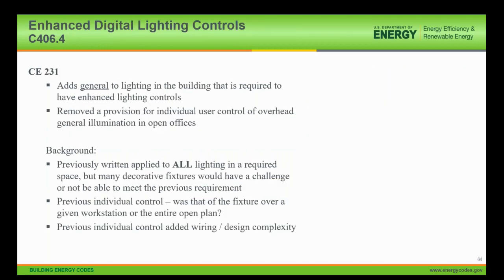Beyond occupancy sensor controls, there's also the enhanced digital lighting controls. This is again some clarification text. It adds the word general to lighting so that defining on what types of lighting needed to apply and meet those requirements for the enhanced lighting controls. And it also removed a provision for individual user control of overhead general illumination in open offices again. As previously written, it applied to all lighting.